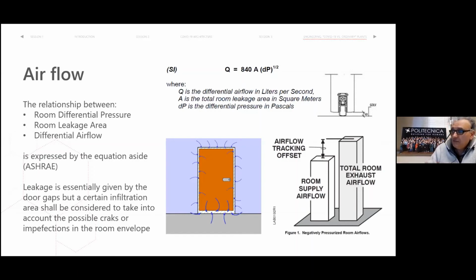So it is very important to have a door which is very well tightened to the frame. The gasket all around must be of high quality, and then another very important thing is to control the infiltration on the bottom of the door, which moves over the floor. And so in this case, it is essential to have a sliding gasket like this that moves up and down and keeps the gap closed. So it is anyway similar to a gasket. Of course, it can slide over the floor, but it's very important.